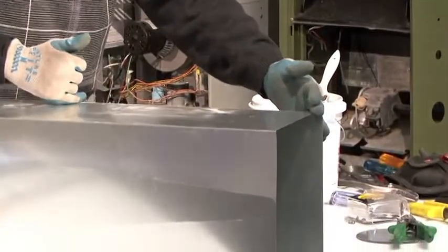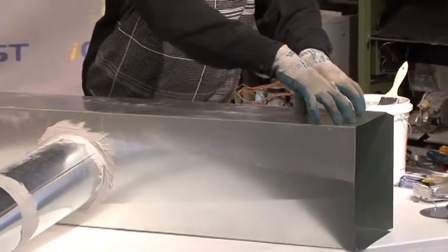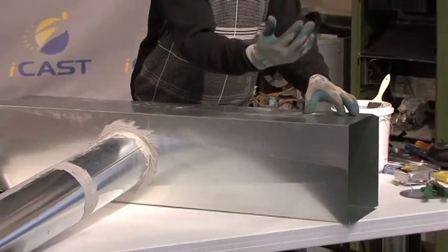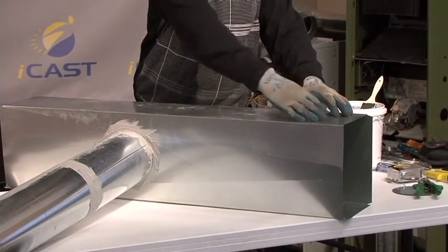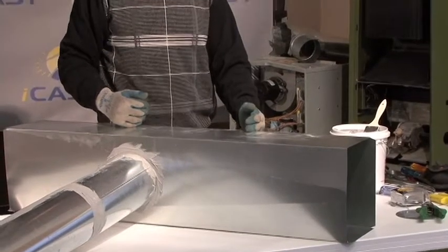Does it matter how close the first vent is off the furnace? Yeah, static pressure. Like if this is the end right here, I wouldn't tap in here. You got to go at least a foot above. It's kind of a rule of thumb, the foot. Don't just come right here at the beginning of it and tap off of there because you're taking the majority of the air from it. So I would say we have a foot rule or more to tap into it.